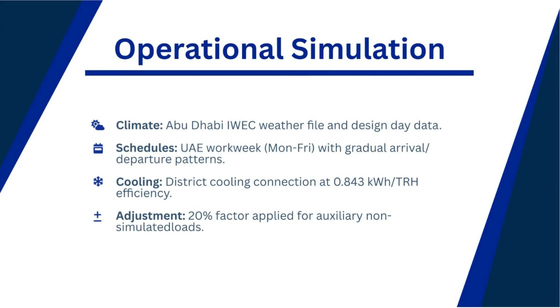The operational energy and embodied carbon analysis compares the baseline model, B0, with the retrofit scenario, R1. For the baseline, the building shows a high energy use intensity of 133.7 kilowatt-hours per square meter per year. Cooling demand dominates, accounting for roughly 72% of total consumption due to the hot climate and inefficient envelope performance.